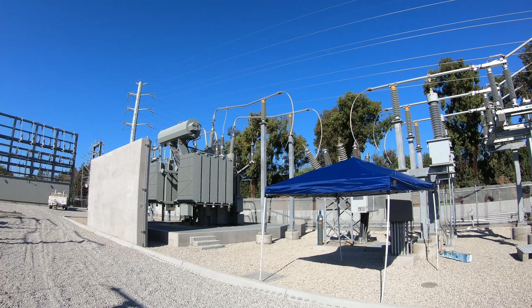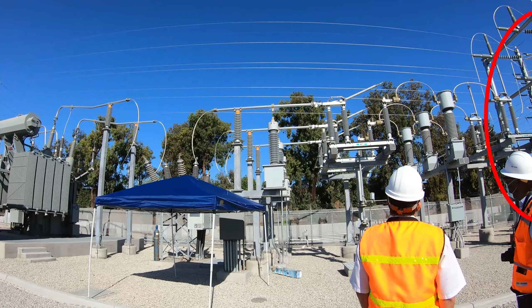That transmission line is 115,000 volts, and it's connected at the first portion of the substation to the PG&E switchgear. There's a control building at the beginning of the station which allows PG&E to monitor and to remotely control that input into the substation. Ultimately, the entire substation will be automated and non-manned.